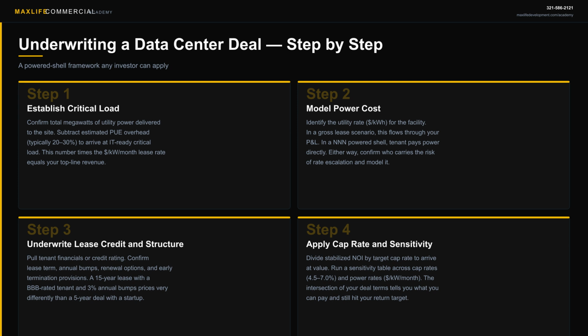Step 1 is establishing critical load. You need to know exactly how many megawatts of utility power are delivered to the site, and then haircut that for PUE overhead. If the facility draws 12 megawatts from the grid and has a PUE of 1.2, you have 10 megawatts of critical load available to IT equipment. That 10 megawatts times your lease rate per kilowatt per month is your top line revenue. Everything flows from that number.